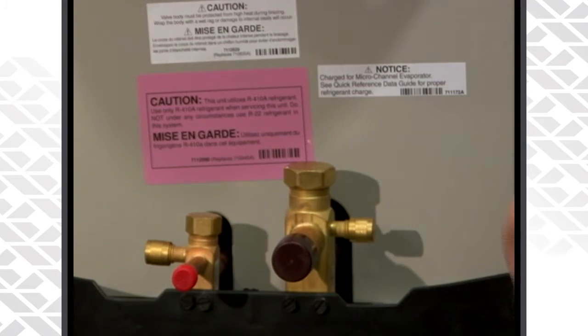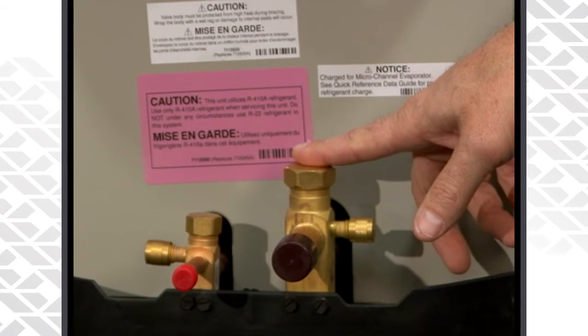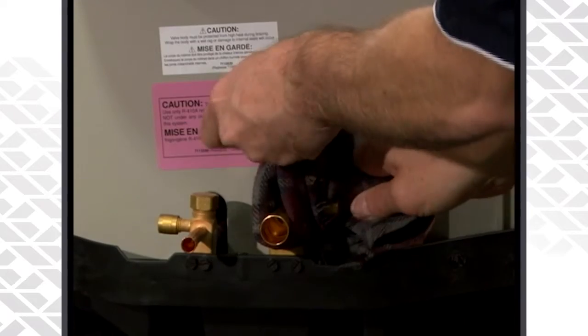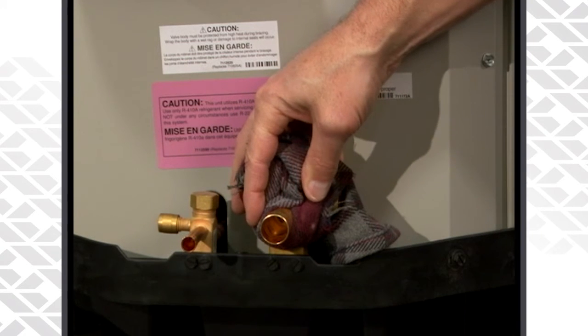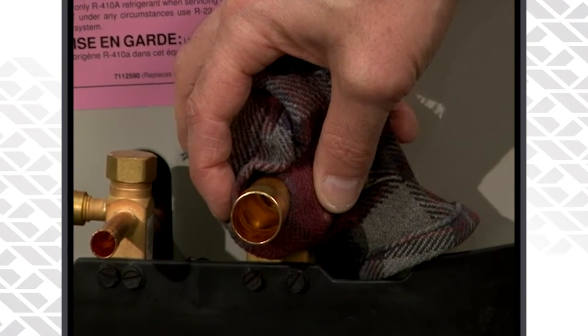One of the main things we want to keep in mind is that we want to protect our service valves from any excess heat. Make sure you use a wet rag — Nordyne recommends a wet rag when brazing on the service valves. Don't use some of the pastes that are out there, thermal paste or anything like that. Just use an old wet rag to keep some of that heat away from the body of the service valve.